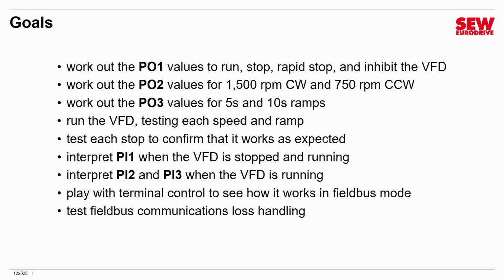Then I'm going to run the VFD and test each speed and ramp. I will test each stop to confirm that it works as expected. I will capture my process input word 1 when the VFD is both stopped and running, and I will interpret what the bits mean. And then I will interpret process input words 2 and 3 when the VFD is running. Finally, I'm going to play with terminal control to show you how it differs from regular terminal control.